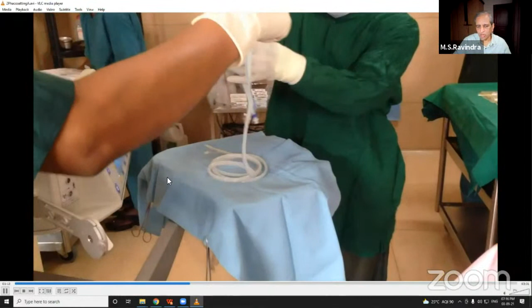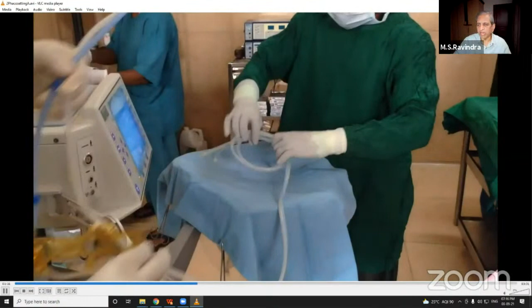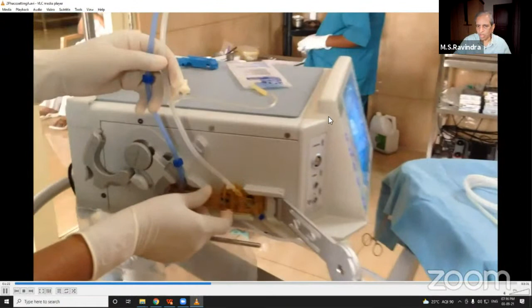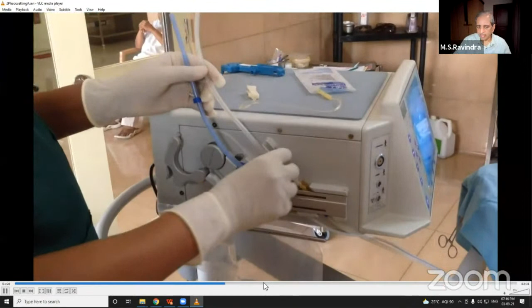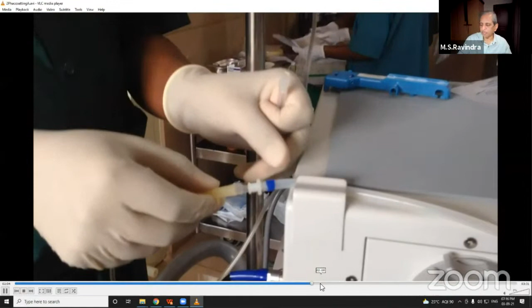And as you see, when you buy a phaco machine, ensure that the cassette can be autoclaved. Do not buy a machine where they say you have to buy a cassette for every case and you end up reusing it. So this is a phaco. I have no commercial interest, but this cassette can be autoclaved any number of times. If there are 5 cases, autoclave it 5 times. We have 4 sets. You buy 4 hand pieces, 4 tubings, and recycle them.